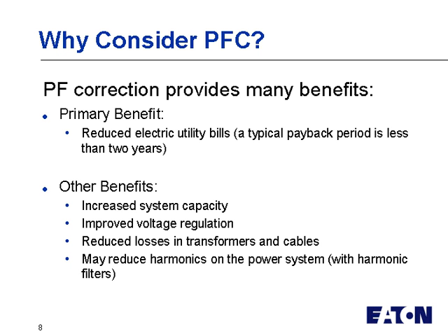Why do we consider power factor correction? Well, the primary benefit really is to reduce the electric utility bills, and a typical payback may be less than about 2 years. Other benefits, though, we mentioned we're going to talk about other benefits. You can increase system capacity. For example, if you have double-ended substations, you can actually increase the system capacity to where you can provide all of the load off of one transformer.